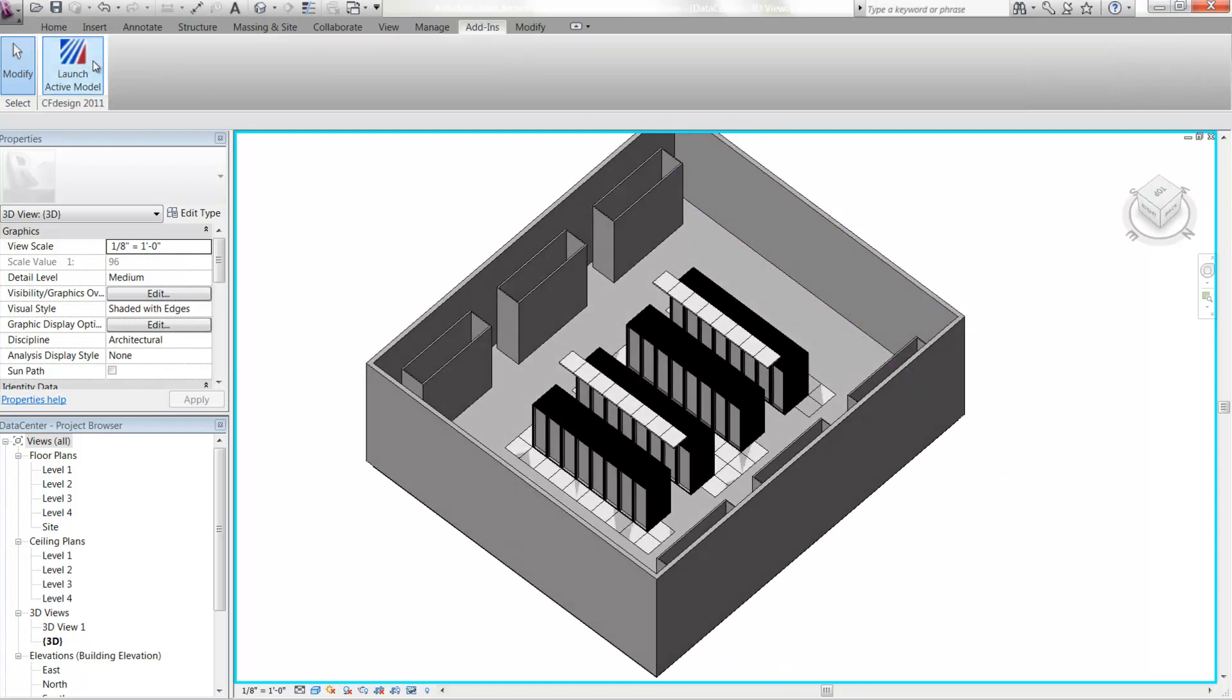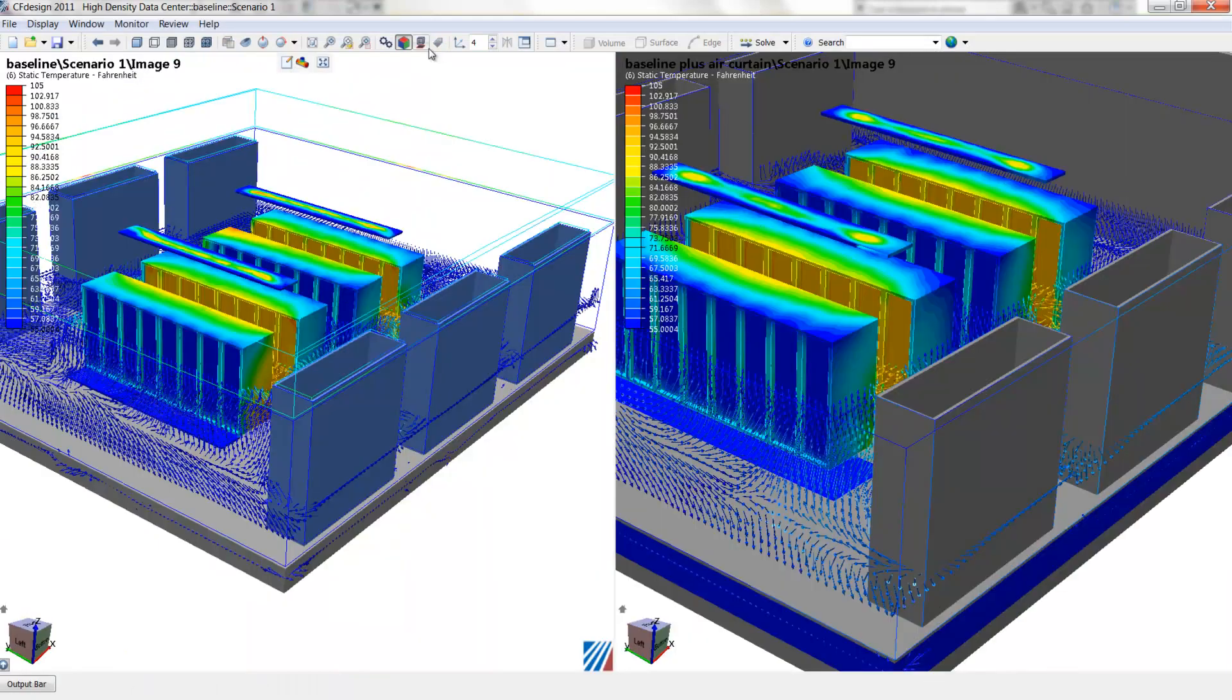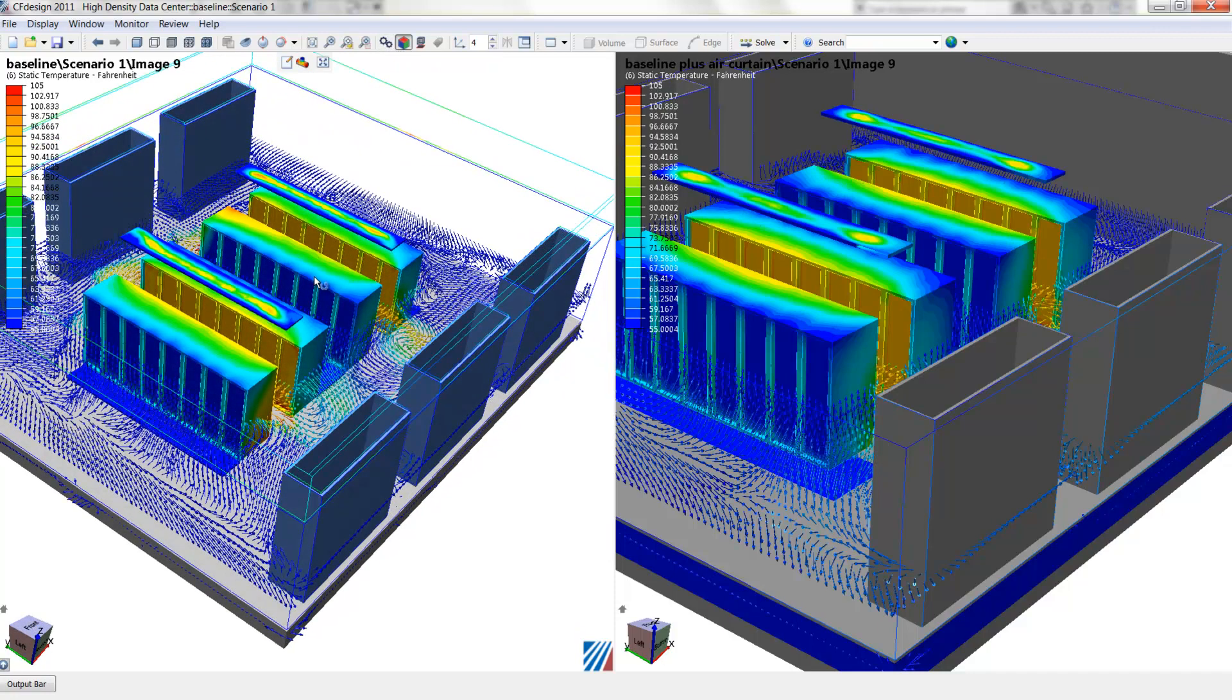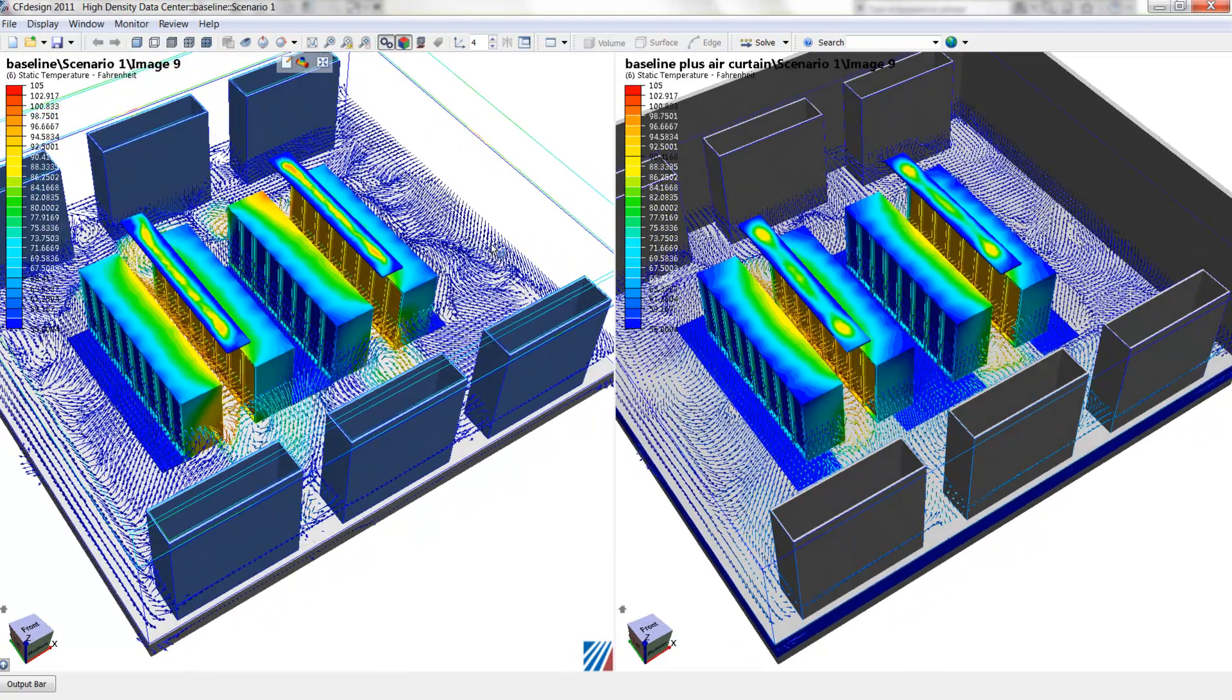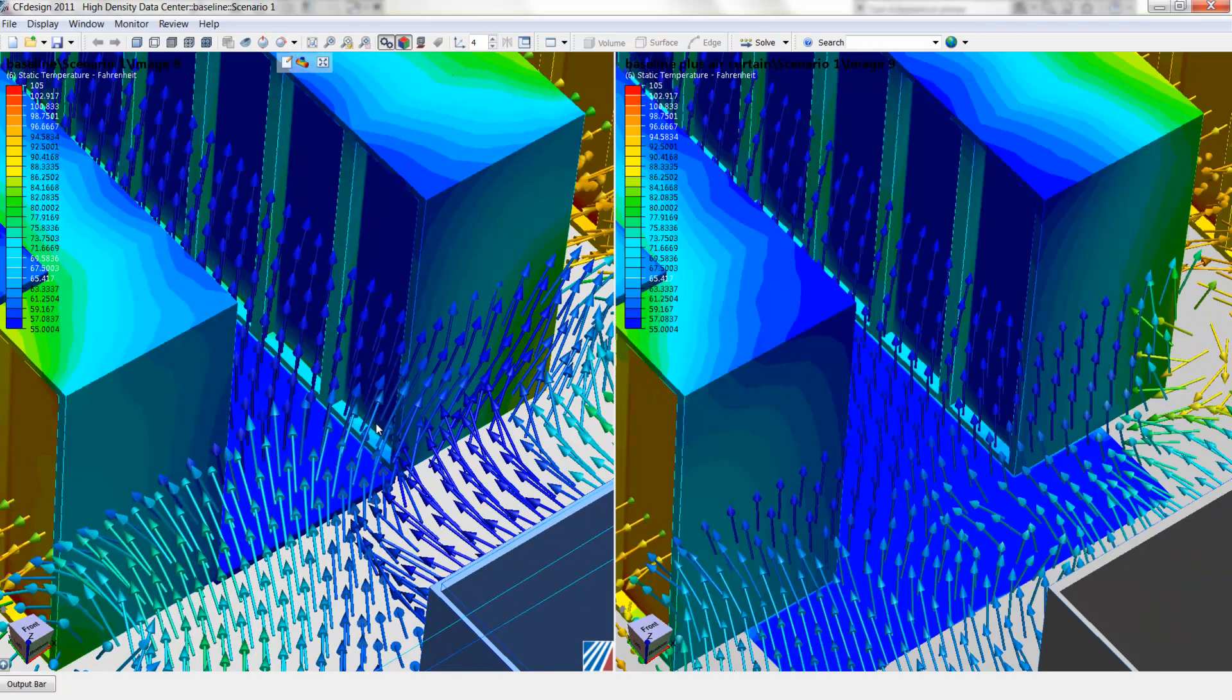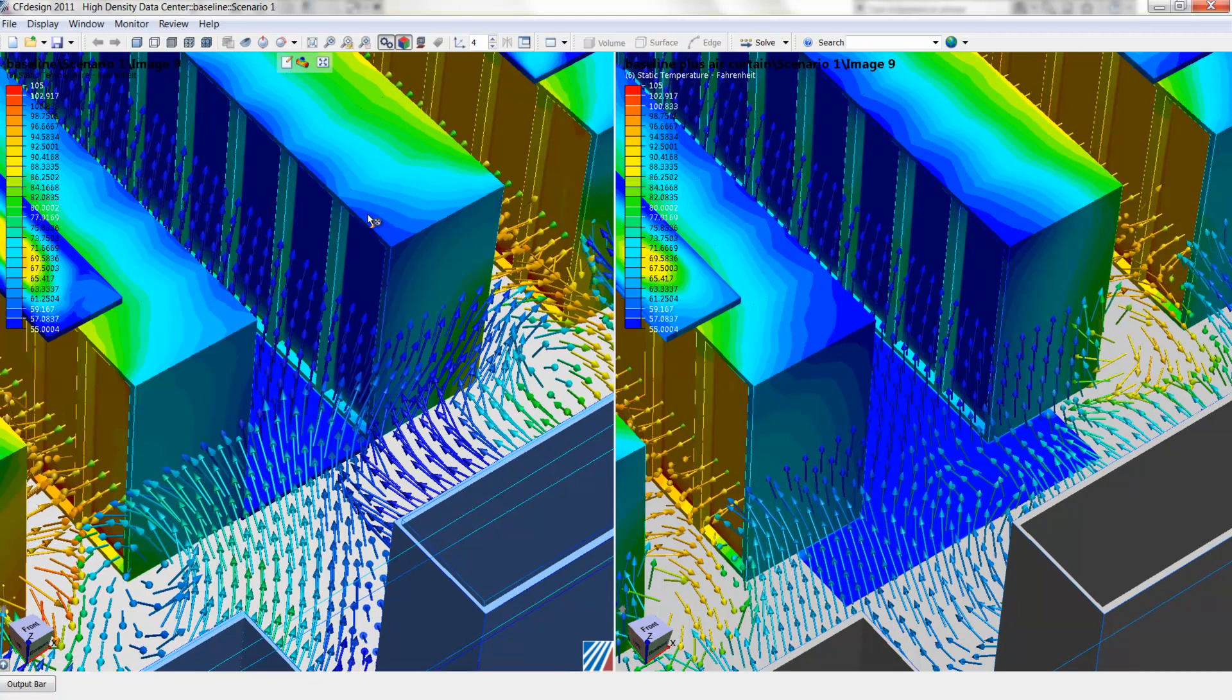And now we can compare the performance of the two designs side-by-side within CFDESIGN. On the left, we have the baseline without the air curtain. Again, this is for new construction. And on the right, we have the addition of the air curtain, so we can see the recirculation effects are mitigated or reduced. And in addition, if we spin this around and look at temperature distributions on the racks, their maximum temperatures have been reduced as well.